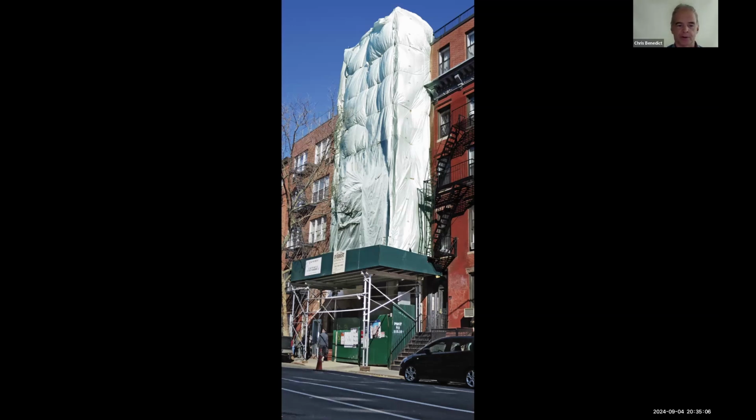It's winter, so you can tell without looking at the guy with the jacket on, you could say, ah, that must be winter because the tarp is puffing out at the top and pulling in at the bottom. So that shows you the magnitude of the force that pulls air in the bottom of a 5-story building and pushes air out the top of a 5-story building.